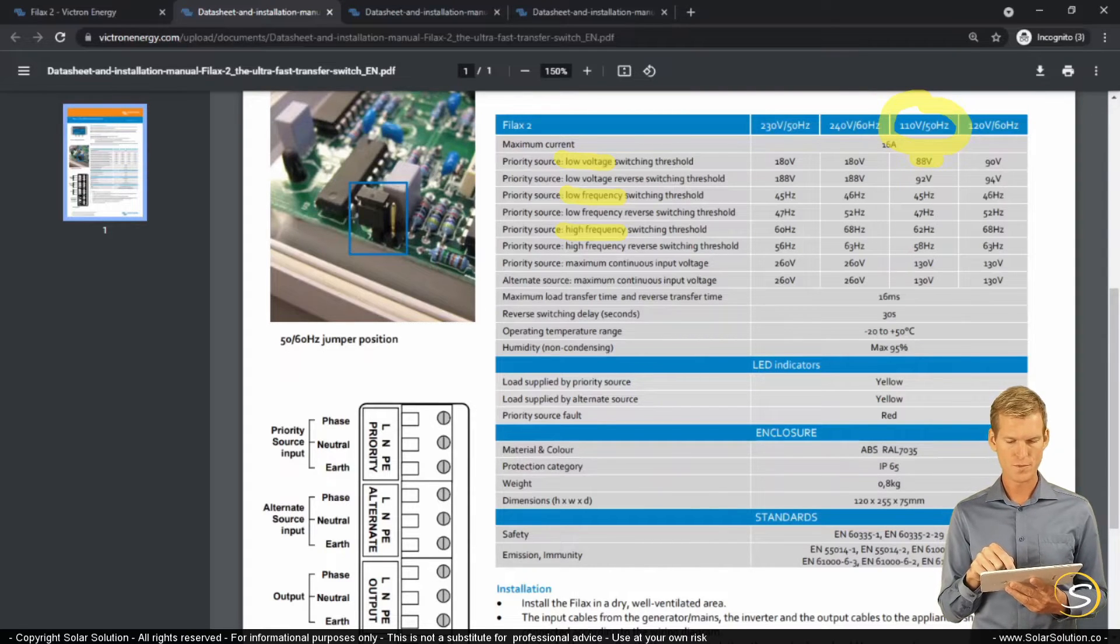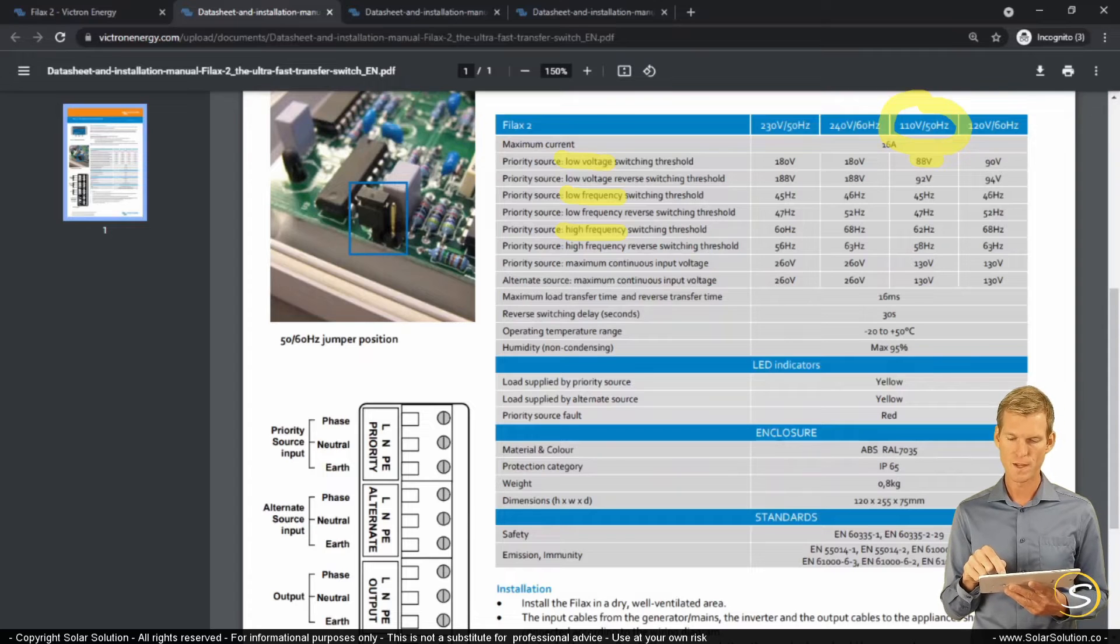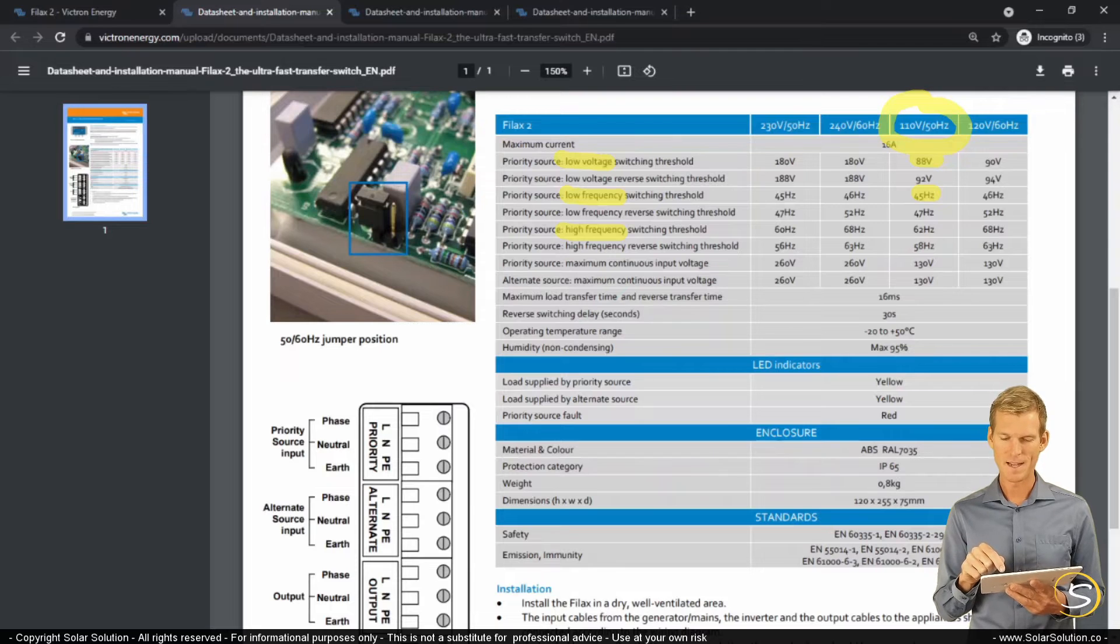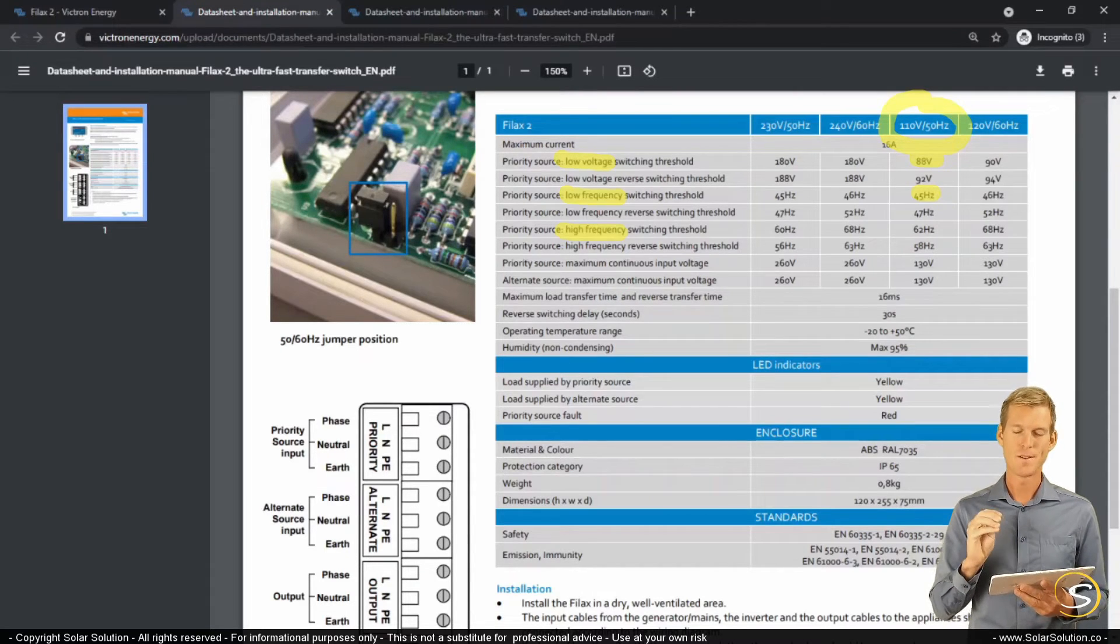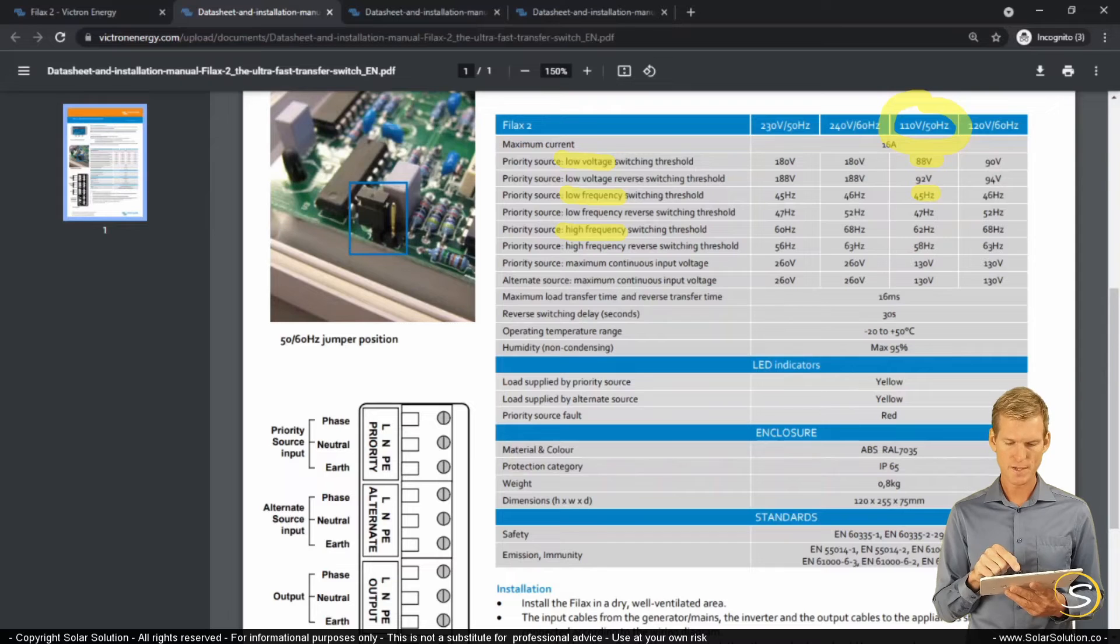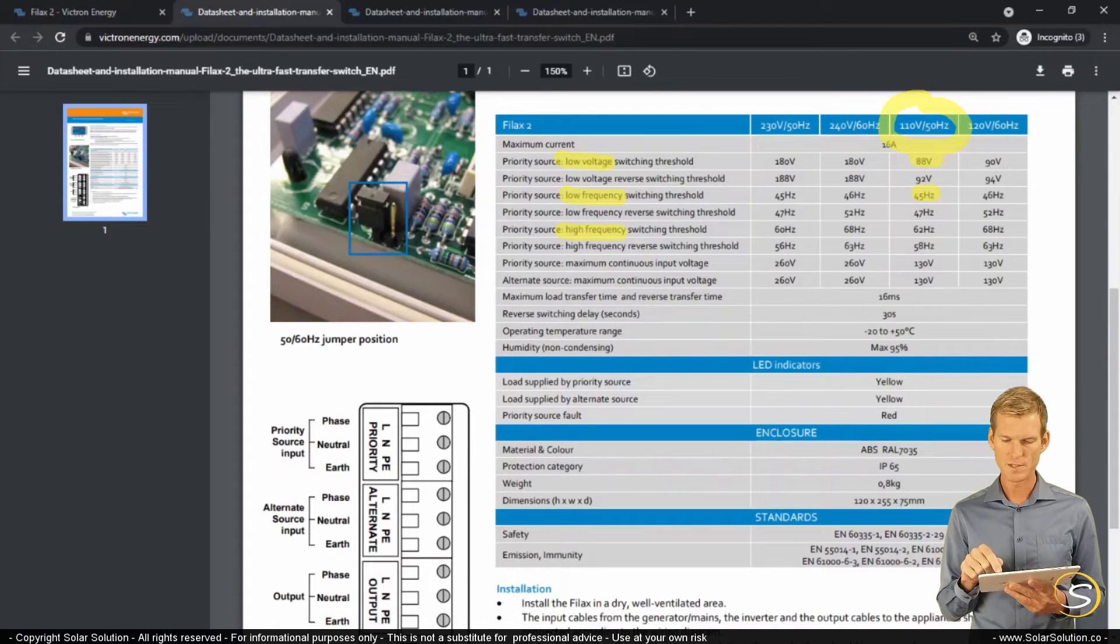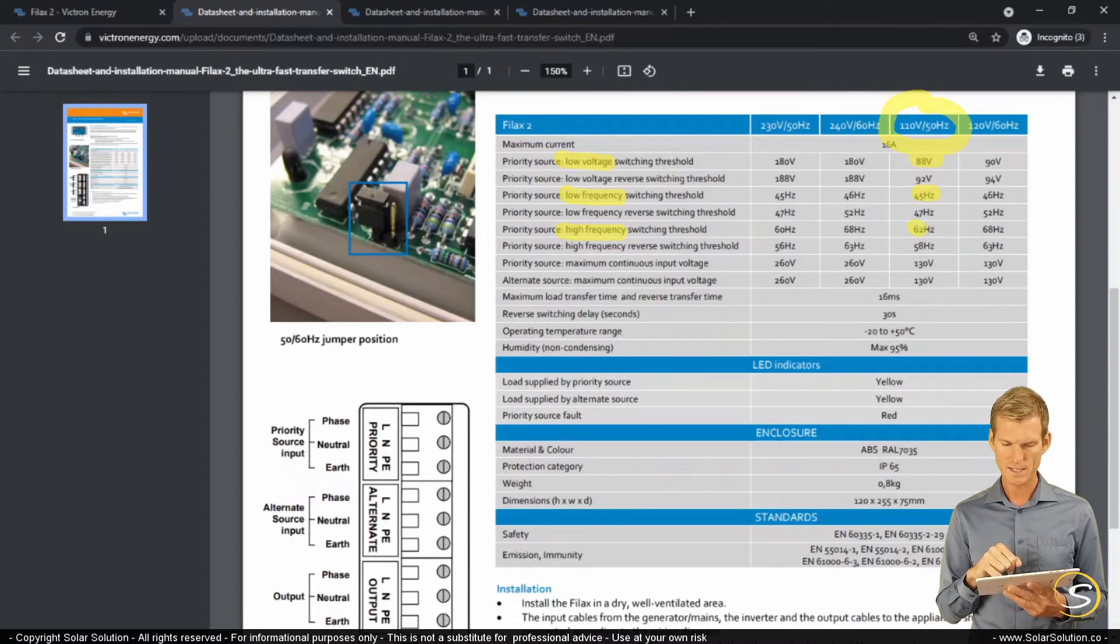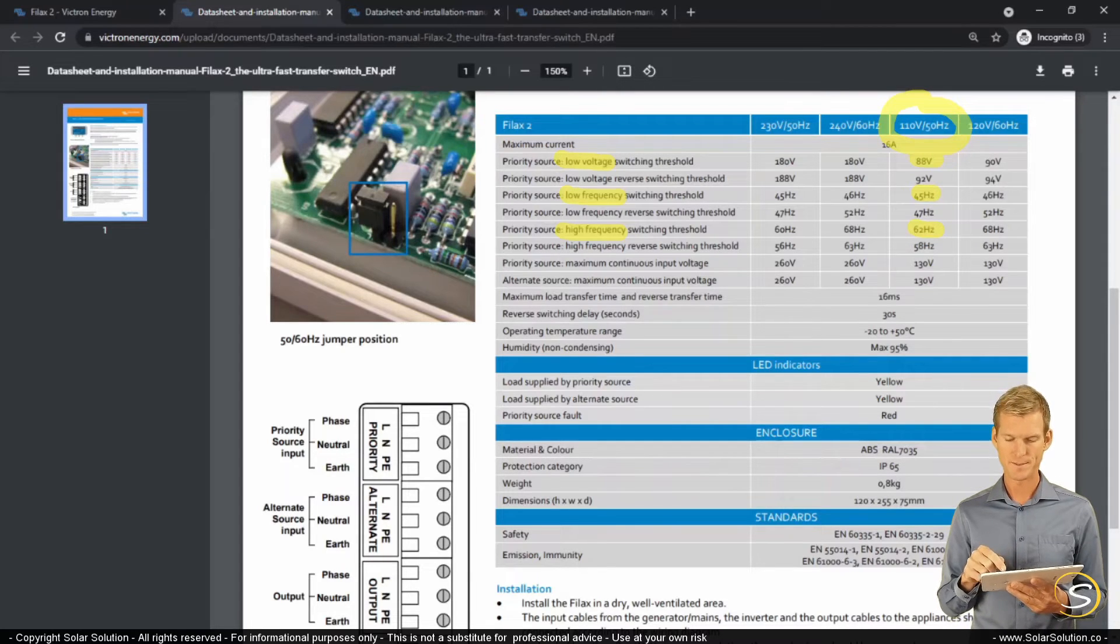It will also switch if the frequency is lower than 45 hertz, which by the way is really, really low. Having a voltage slightly out of the parameters is troublesome, but not as troublesome as having your frequency out of these set parameters. So this will switch between your primary and your secondary source if the frequency is below 45 hertz. Or if the frequency is too high, if it is 62 hertz or higher, then it will also switch towards your generator.